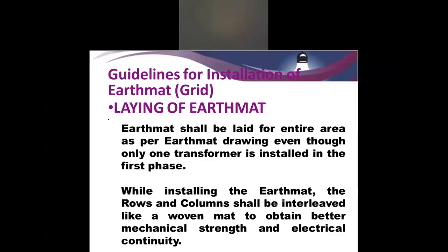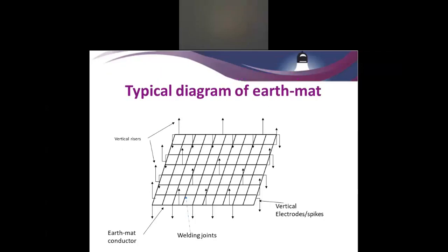So based on the earth mat drawing, we carry out the earth mat. A typical diagram of an earth mat is like this: we have rows and columns running of GI flats, and there will be vertical electrodes - these are rods that penetrate into the ground, around 2 meters deep.